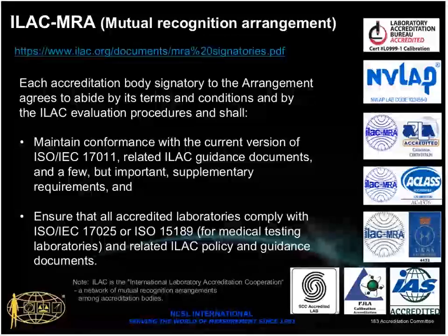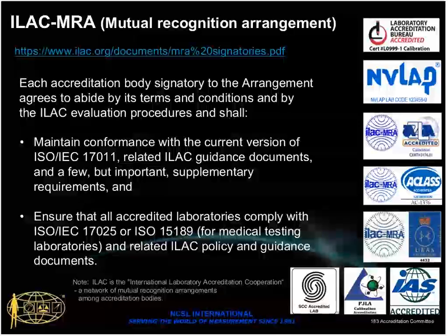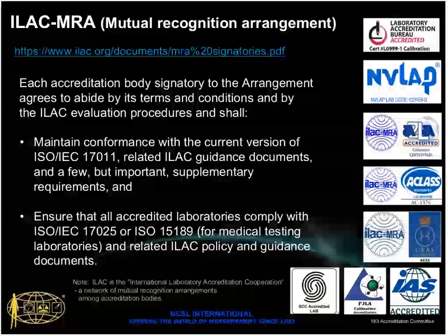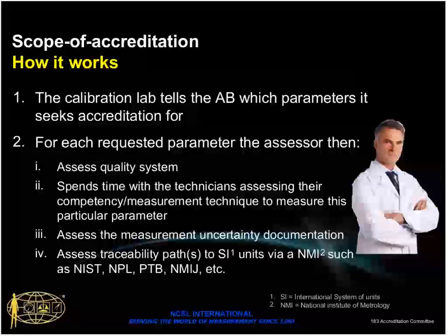If we just go back for a second, if you go to one of those laboratories and you don't ask for an accredited certificate, you are on your own as far as the accreditation body underwriting the credibility of the procedures and of the budgets, etc. But most of the reputable laboratories, and indeed most of the manufacturers and the larger people, will use the same management system throughout their operation. But I would always suggest that you ask for an accredited 17025 calibration, but you are free to ask for a variant, which might be less in some ways and wouldn't bear the accreditation mark. But if you go to an accredited laboratory, you can be sure that the competence is there in the organization.